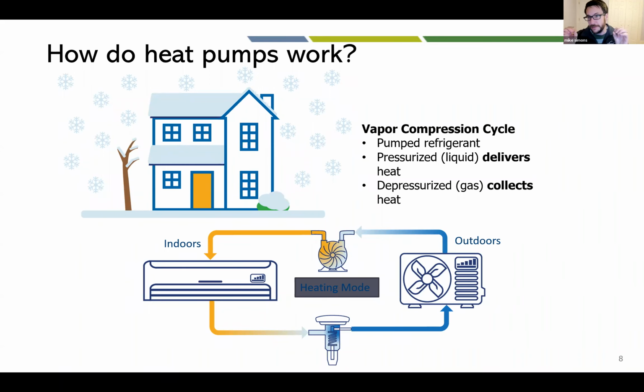And what's going to happen is there's this equation: as you increase pressure, it equals increased temperature. So really what's happening is on the outdoor unit, it's picking up the energy in the outdoor air. Say if it's 0 degrees outside, the outdoor unit is going to have -30-degree refrigerant in it. Hot goes to cold, so the 0-degree air is going into this -30-degree refrigerant, and eventually that refrigerant is going to be 0-degree refrigerant.